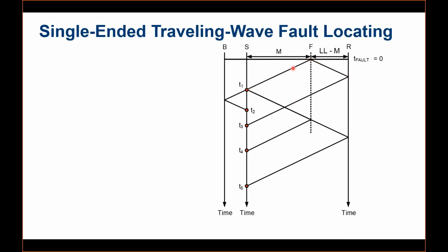Once the wave travels and touches your point S, it's at T1. The relay will time-stamp that point, and after the reflection, it will go back and hit that fault point again. The fault is a change of impedance, and it will travel back. So if the traveling wave is stronger, it can come back and bear one more reflection, and it can come back again.